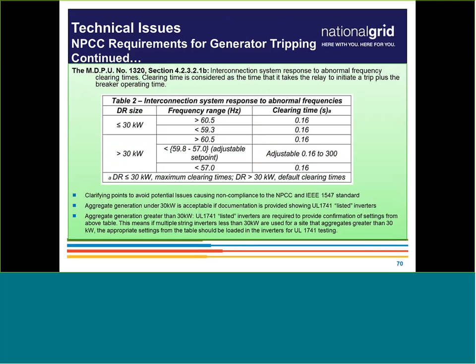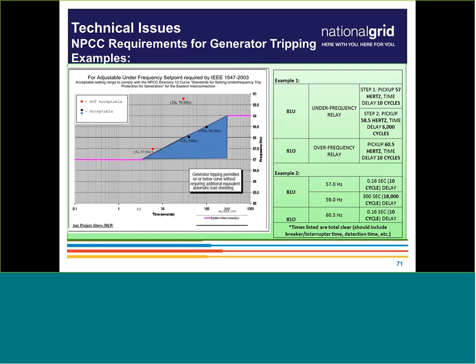You do have these ones right here. We look for 2 under frequency settings and 1 over frequency setting. 2 of them are pretty much defined already, but it's up to you to choose what goes in the triangle here. These 2 settings in black are acceptable. These 2 settings in red are above the curve, outside of the triangle, and not acceptable. So we screen for those on the one line, and we'll screen for them on the witness test too, every step along the way, to make sure they're compliant. And that concludes the technical portion.